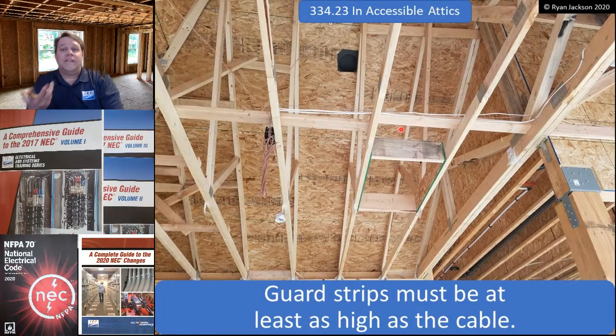Guard strips have to be at least as high as the cable. Makes sense. So you can see here, I enter my attic access and I'm going to be walking around. So in order to satisfy this rule, we have installed these guard strips. What we always just use is 2x4s. You throw a 2x4 up in the attic, and that way I can walk on it and not on the wire.